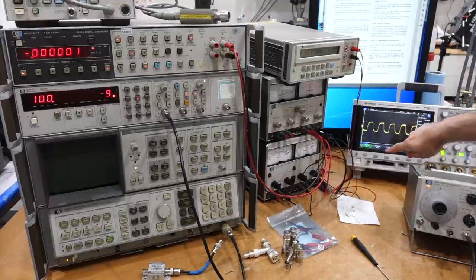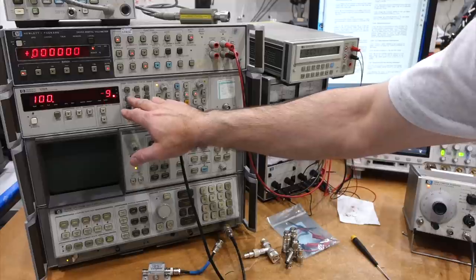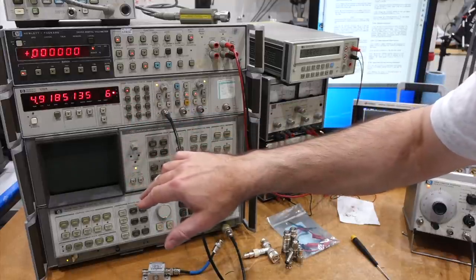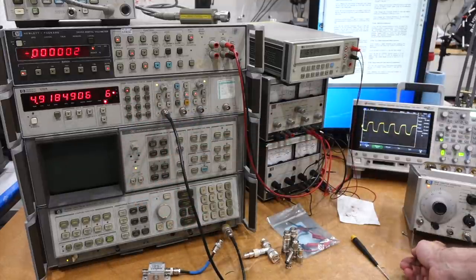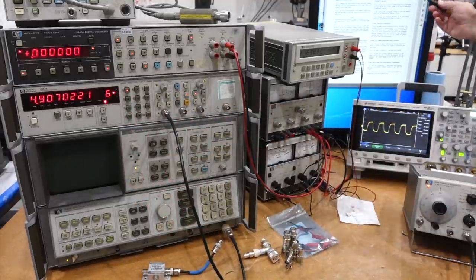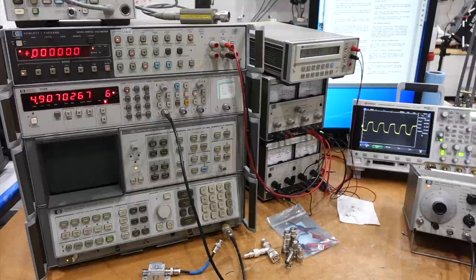Am I at 50 ohm? No, I'm not in 50 ohm. There we go. Okay. If I do frequency, almost. So this should be 5 megahertz. A1R6, this one over here. Other direction. Okay, we're fairly far off. And almost 5 megahertz.